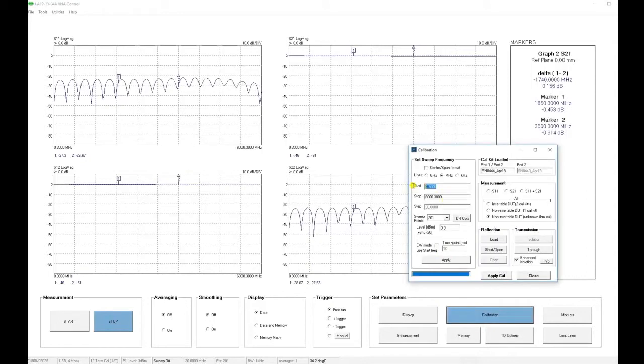Now, we go and set our frequency plan. We are going to use a frequency range that starts at 1,680 MHz, and ends at 2,180 MHz. We are going to use the highest possible test power we have, and that is 6 dBm. We now click apply to load the frequency plan into the instrument.